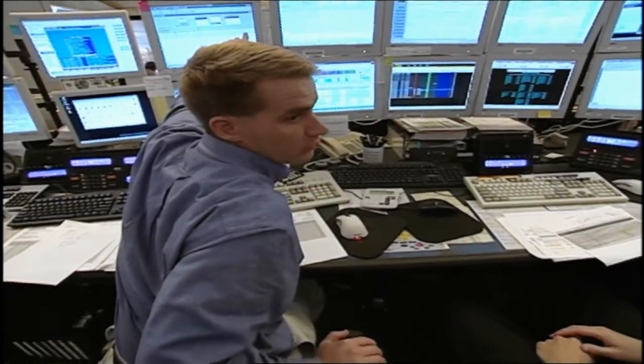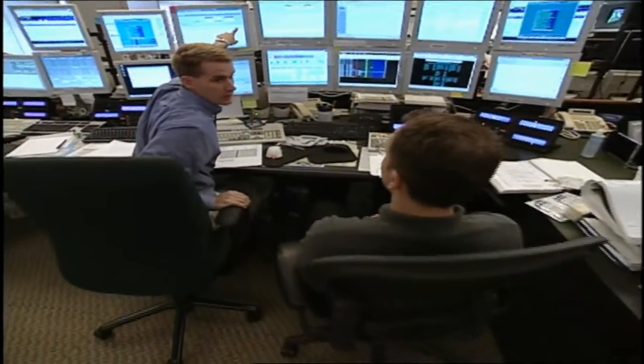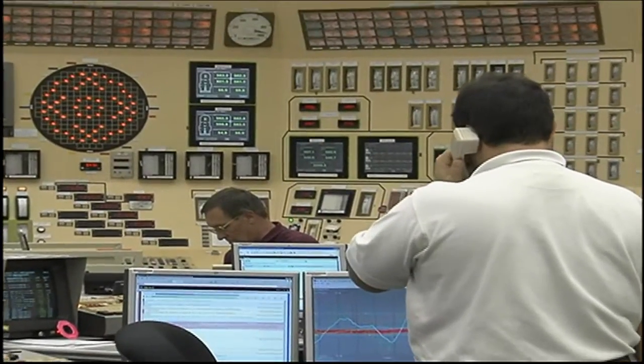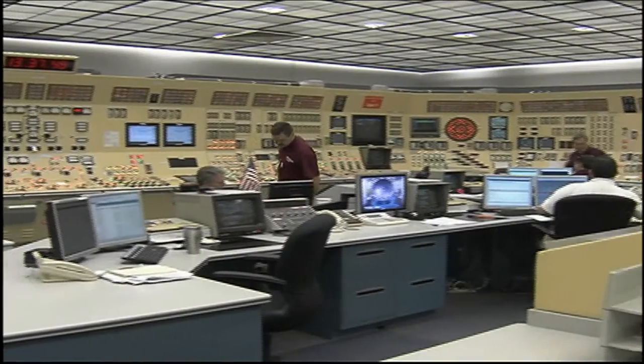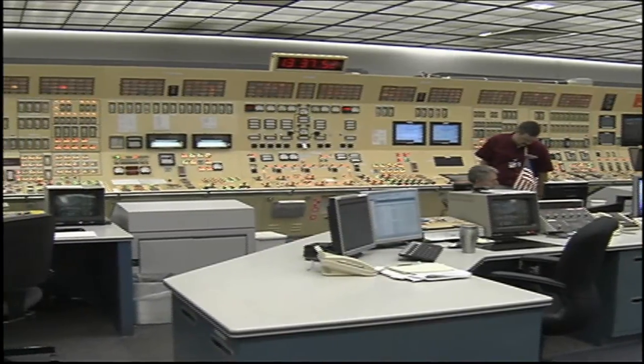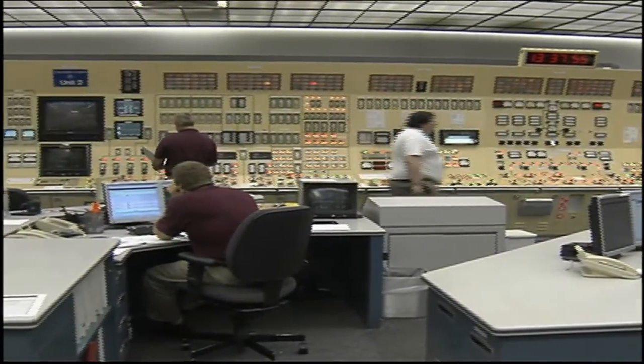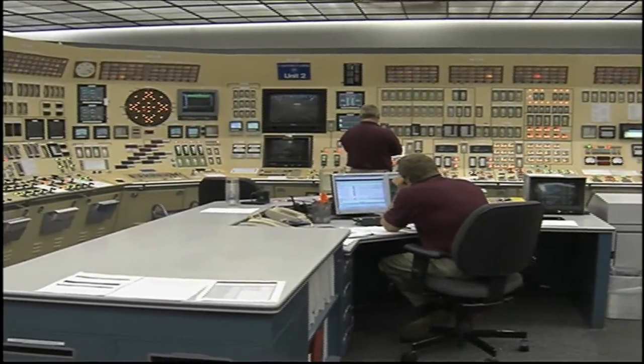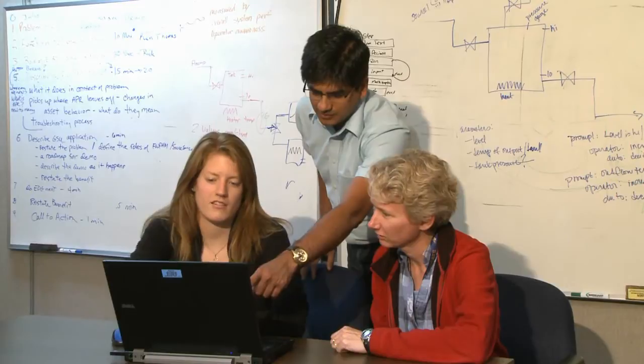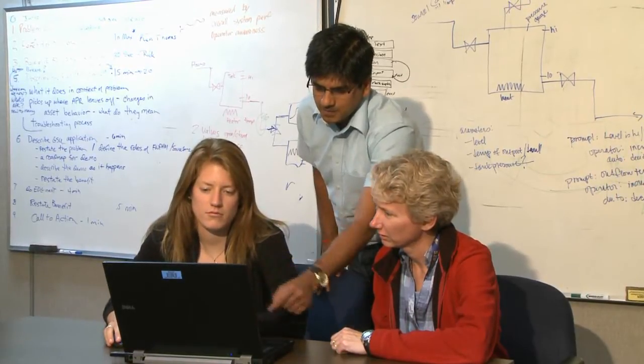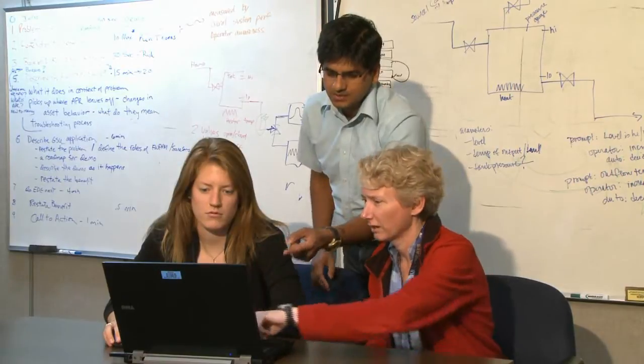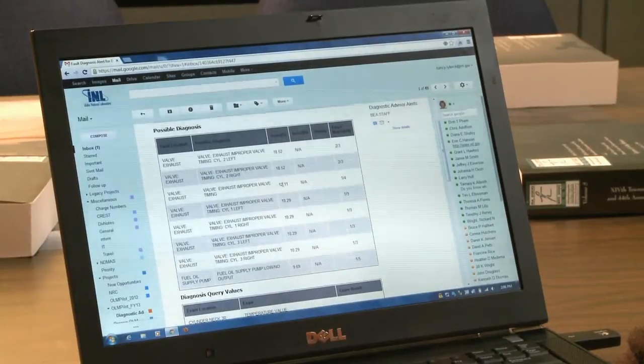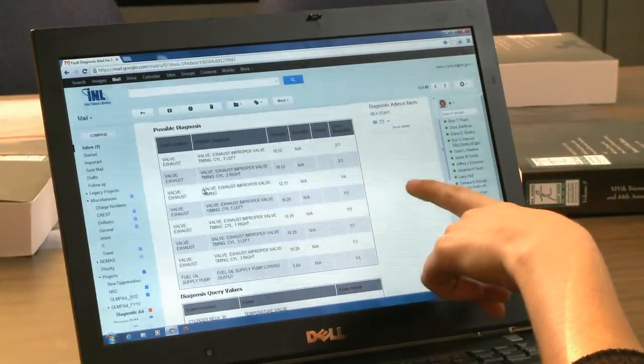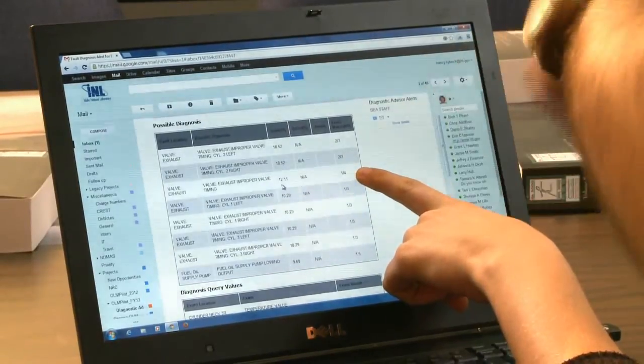Several utilities have deployed monitoring and diagnostic programs for fleet-wide monitoring of their critical assets. These programs provide early detection of abnormal conditions. However, the process of identifying underlying problems still relies on the knowledge of the available staff and often requires other supporting information. EPRI has developed an advisory software system to help plant response teams troubleshoot and resolve equipment problems quickly and effectively. The advisory software system identifies the possible causes of abnormal behavior based on a library of known failures or fault signatures for power plant equipment.